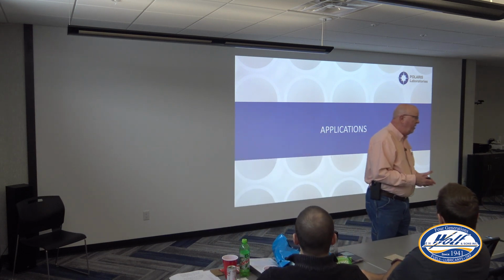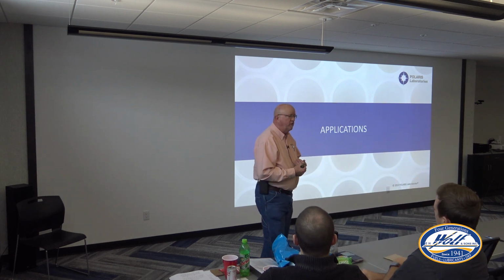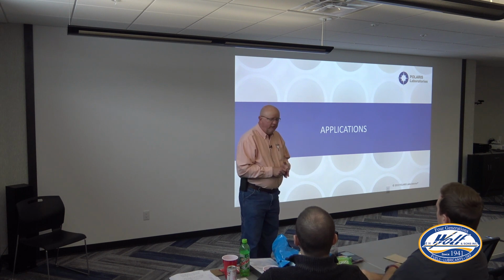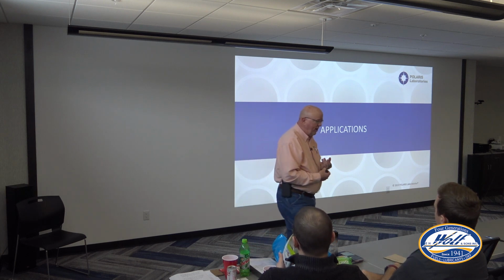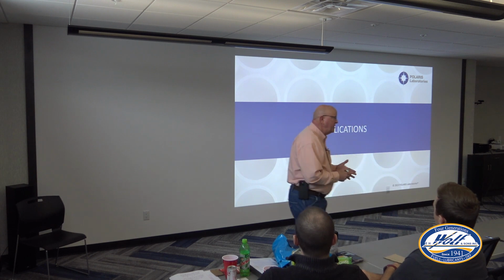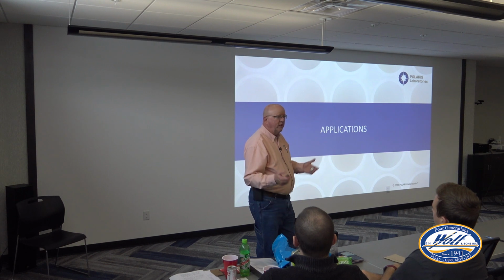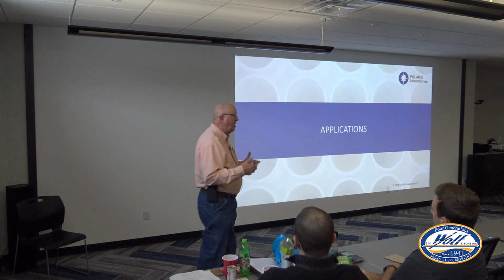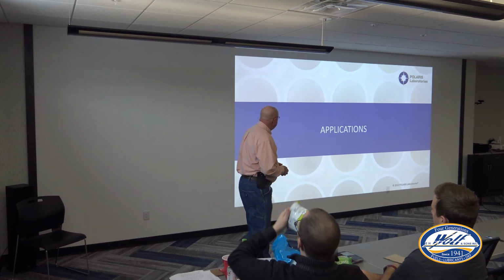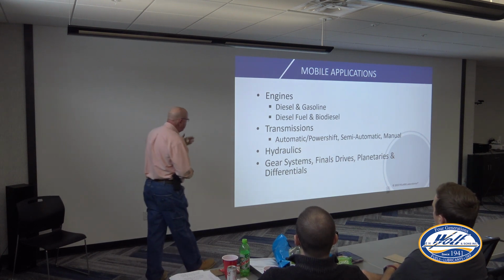I will tell you that I rarely ever recommend a basic package, because for a few dollars more, you can get an advanced test package and get so much more information. The only time I typically would recommend a basic, and where I've seen it happen, is if you get into a state bid or something like that, and they limit you. They say, this is what we want for oil analysis, these are the tests we want, and usually it turns out to be a basic test. I don't see them doing a lot of advanced testing. So I always say, go for the advanced test package. It's money well spent.